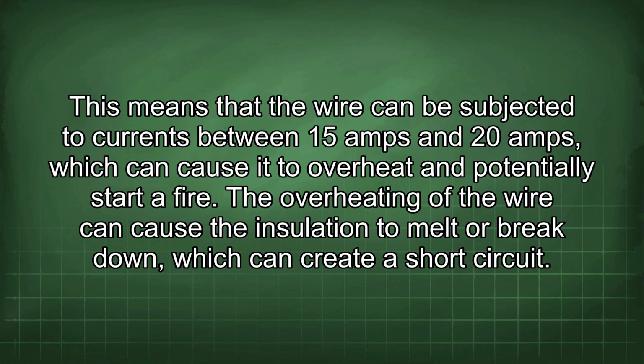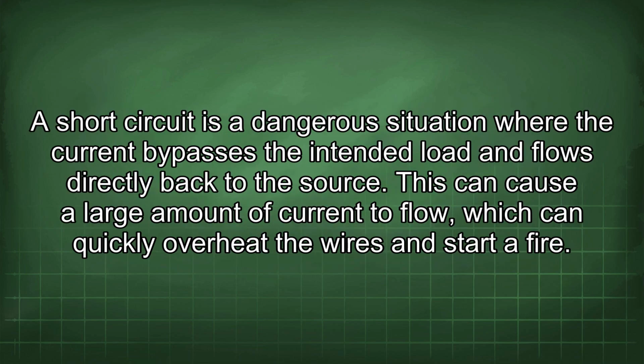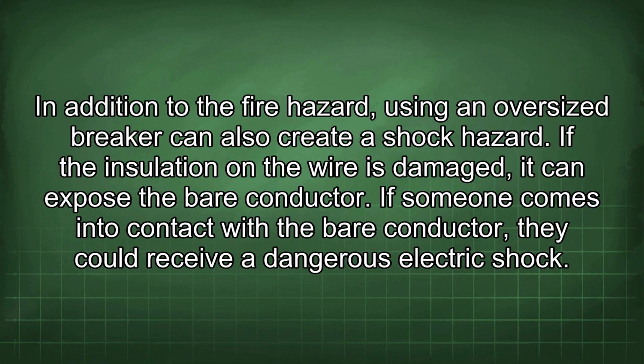This means that the wire can be subjected to currents between 15 amps and 20 amps, which can cause it to overheat and potentially start a fire. The overheating of the wire can cause the insulation to melt or break down, which can create a short circuit. A short circuit is a dangerous situation where the current bypasses the intended load and flows directly back to the source. This can cause a large amount of current to flow, which can quickly overheat the wires and start a fire. In addition to the fire hazard, using an oversized breaker can also create a shock hazard.